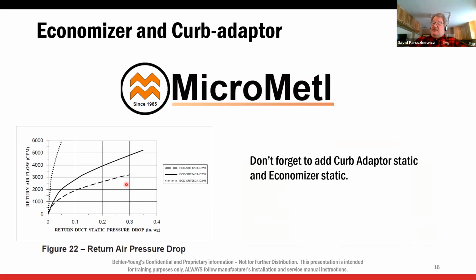Don't forget the economizer and the curb adapter. There is a static amount for the economizer and the curb adapter. It'll be in the paperwork. So when you get the economizer, if you look at it, you'll see from the CFM you have, so 2000 CFM, that tells you what the static is. So add the static for the economizer and the curb adapter.